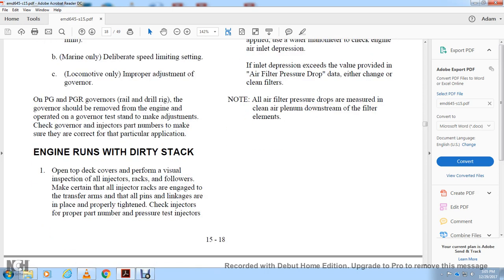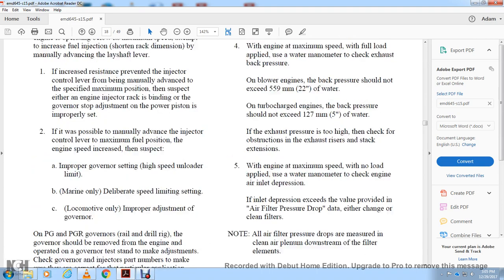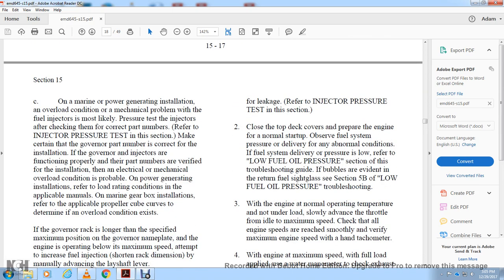Engine Runs with a Dirty Stack: Open the top deck cover and perform a visual inspection of all injectors and racks for proper positioning. Make sure all injector racks are engaged in the transfer arm with all pins and linkages in place and properly tightened. Check injector part numbers and pressure test injectors for leakage — refer to the injector pressure test inspection. Close the top deck cover to prepare the engine for normal start. Observe fuel system pressure or delivery for any abnormal conditions. For low fuel oil pressure, refer to the troubleshooting guide. Return fuel sightglass to section 5B of the low fuel oil pressure troubleshooting.